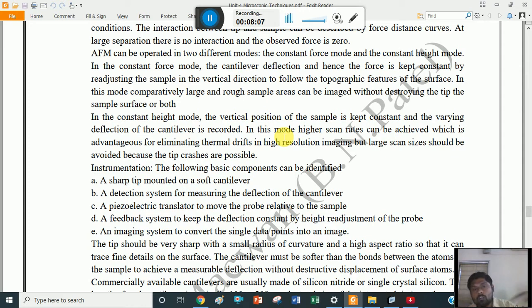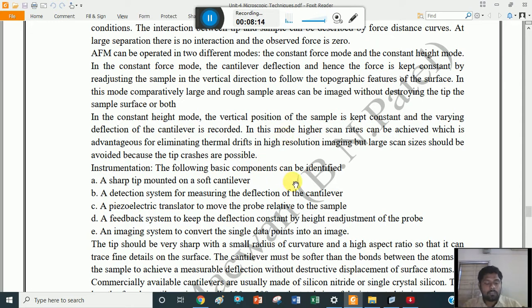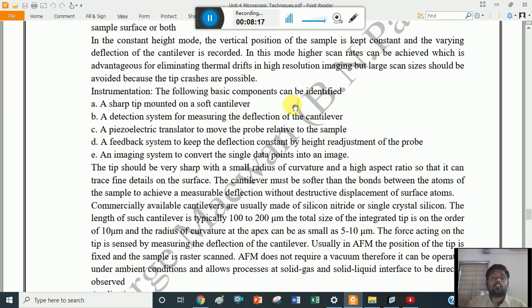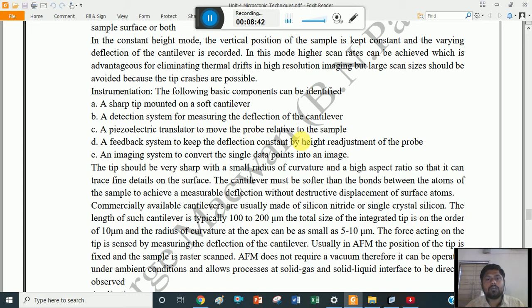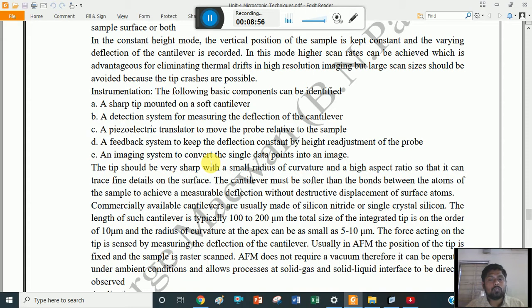When the tip moves vertically above the surface of the sample, sometimes the tip may be damaged. For instrumentation of AFM, the following basic components can be identified: a sharp tip mounted on a soft cantilever; a detection system for measuring the deflection of the cantilever; a piezoelectric translator to move the probe relative to the sample; a feedback system to keep the deflection constant by height readjustment of the probe; and an imaging system to convert the single data points into an image.